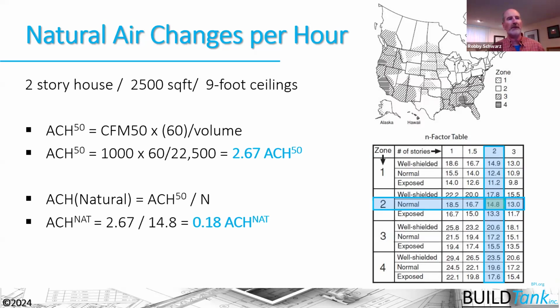Now, when we convert that to a natural air change number, we get 0.18 natural air changes. And how we convert that is we have to go to the chart on the right here, and we have to get the conversion multiplier or divider. I guess it's a division. I'm sorry. So in this case, it's in zone 2. It's normal shielding. There, it's a 2-story house, and we get a 14.8 number that we have to divide our air change number by, and that gives us the 0.18 number.